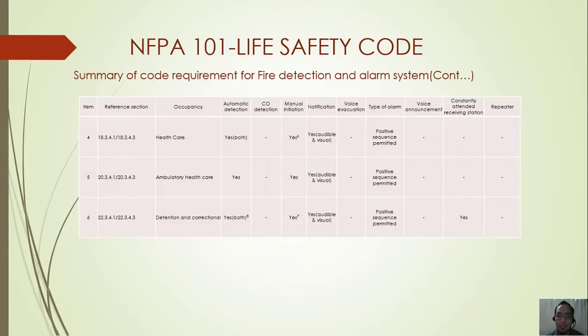Manual initiation, yes, it's required. Notification, yes. Audible and visual, no requirements for voice. And type of alarm, positive sequence, yes, it's permitted.